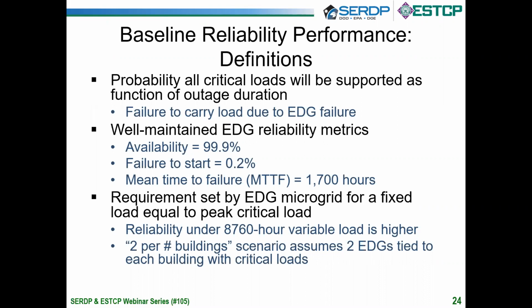There are three reasons that a generator may not be available to support the critical load. First, it could be not available. That is, it may be offline due to required repair from some previous failure or from a maintenance event. It can fail to start, which is quite a common event for poorly maintained generators, and it can fail while running. These reasons need to all be considered when looking at the reliability of generator-based systems.